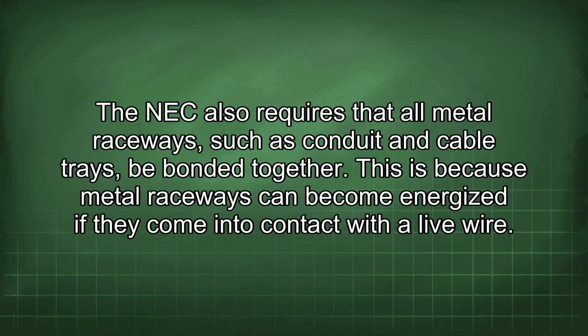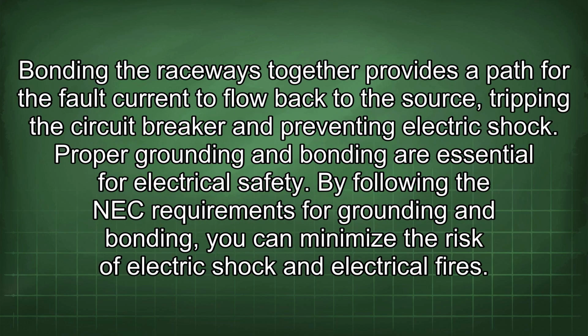The NEC also requires that all metal raceways, such as conduit and cable trays, be bonded together. This is because metal raceways can become energized if they come into contact with a live wire. Bonding the raceways together provides a path for the fault current to flow back to the source, tripping the circuit breaker and preventing electric shock. Proper grounding and bonding are essential for electrical safety. By following the NEC requirements for grounding and bonding, you can minimize the risk of electric shock and electrical fires.